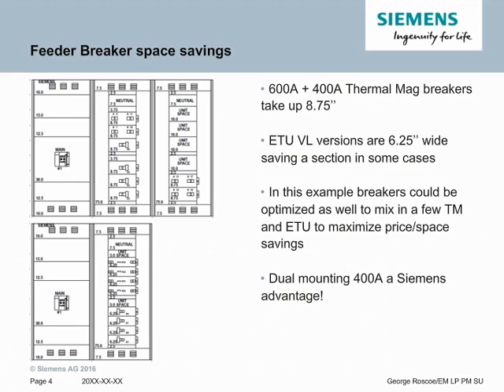And this illustration shows how you can save a section using that option. That option may not always work, so it should be experimented with to see, based on price and section, to get the proper balance. Another key feature illustrated here is a Siemens advantage. We are the only company that can dual mount 400 amps in less than 40 inches of section width. You can see that used several times here to save space and it is a very big competitive advantage for us. This specific example shows 400 amp breakers mounted in 38 inches wide sections. That is a key advantage to save space, in addition to the previously discussed thermomagnetic and electronic trip space saving balance.